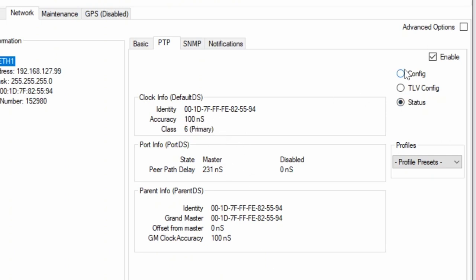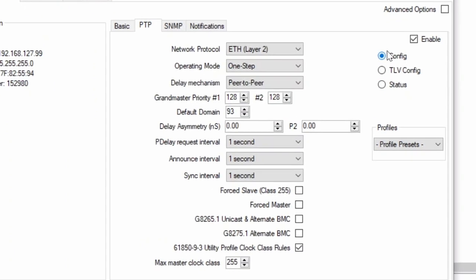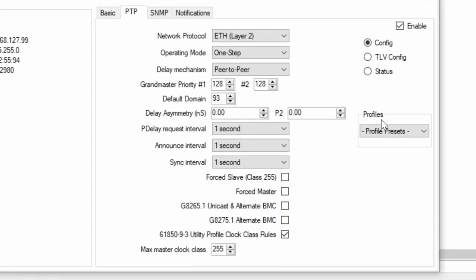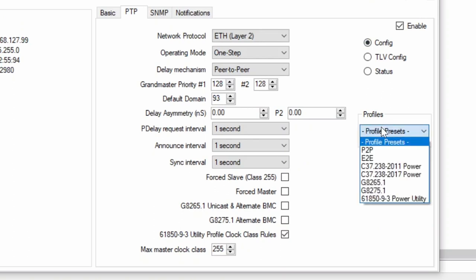PTP protocol provides a lot of different options that can be changed to achieve certain industry requirements. A set of agreed PTP options is called a profile. And for this demo, we are going to use power utility profile defined by IEC 61850-9-3.